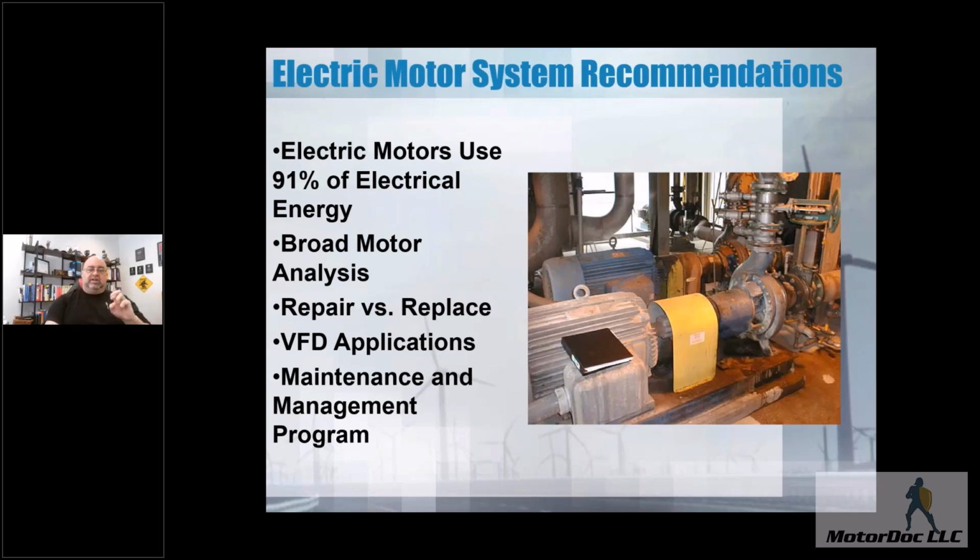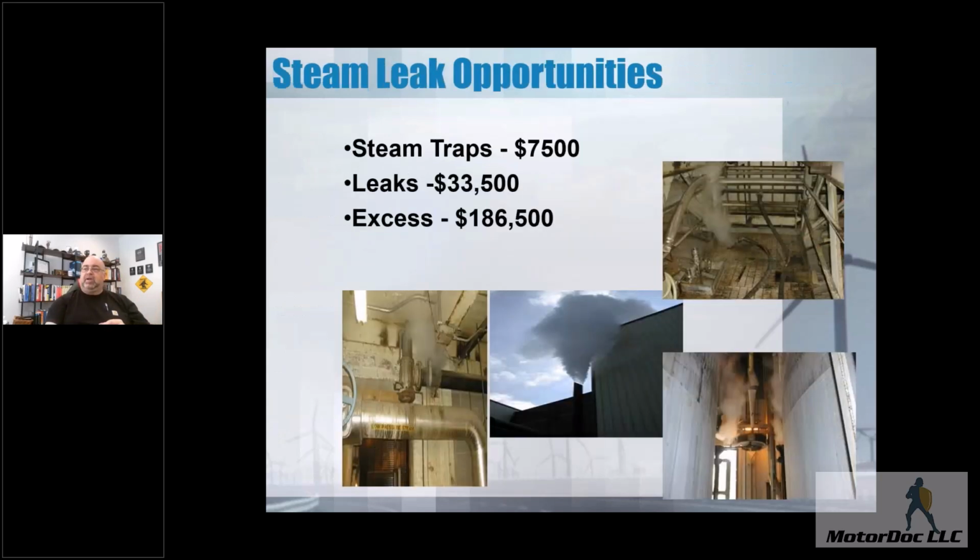So we took a look and saw if there were any additional VFD applications that would work, and we presented repair versus replace options. So they coupled up with a vendor for electric motor replacement, and then also outsourced the storage program, because most of their stored motors were completely useless by the time they went in place because they were in a bad environment.